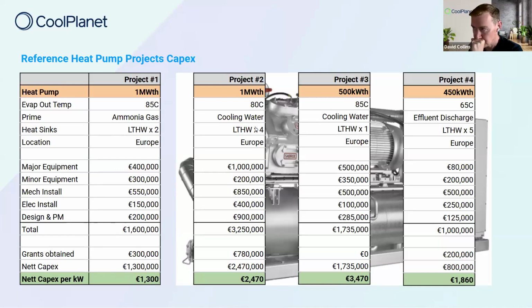The second project here is, again, utilizing cooling water, and it's for a space heating application. So this site was using steam to send around their site, and using steam to hot water heat exchangers to supply their LTHW heating coils and air handling units and to generate hot water. This project interfaced with the return lines on the LTHW, so created a new hot water network. So that's why the cost here would have been that bit more substantial. But you can see there for the scale of the unit installed, 1 megawatt, you're about 2,500 euros per kilowatt installed for that particular project.